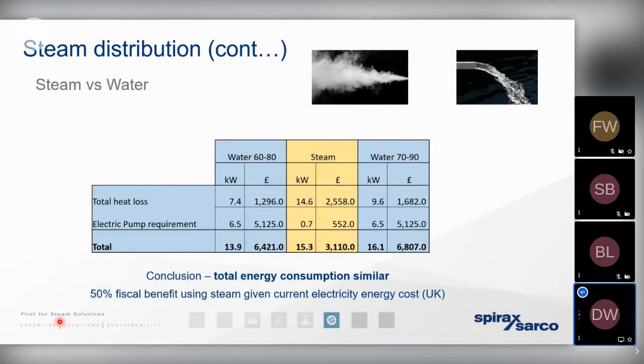Now, there's a very small pumping requirement demonstrated there, 0.7 kilowatt, because it's inevitable that we require an electrical pump to bring the water from the hot well into the boiler itself, maybe even a circulating pump on the hot well just for anti-stratification purposes. So we have factored those small pumping costs in there.